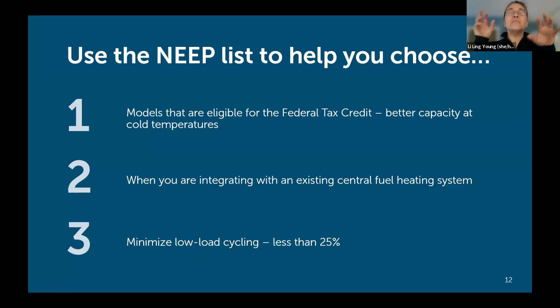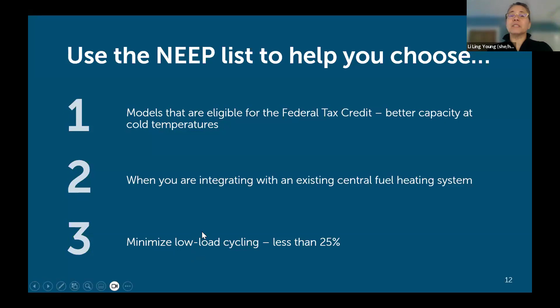And then finally, selecting equipment that has good part load efficiency, so you can minimize low load cycling by creating that chart. It's not specific to the heat pump how much short cycling is going to happen, it's specific to the combination of the heat pump and the building you're putting it in. So it's not always the case that there's one heat pump that's just bad at part load performance, it depends on the building. You have to create the chart to see that, and to my mind, if you can keep it to less than 25%, that's good.